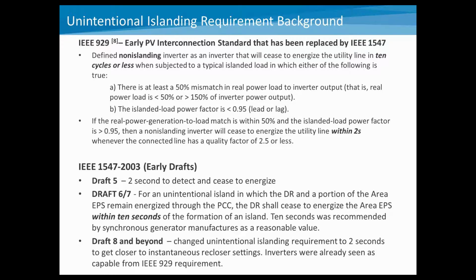So one of the things was a 10 cycle or less disconnection, and that's a really fast disconnection time, but as you can see from the requirements, that applies if the power mismatch is pretty great. And then if the power mismatch is within a certain nominal level, it's within 2 seconds. So that 2 seconds is kind of carried over from early PV interconnection standards.